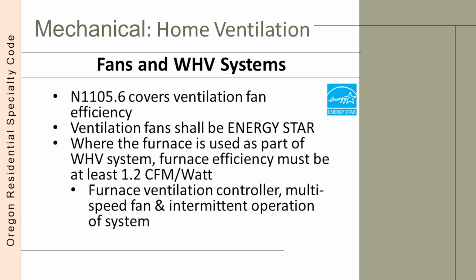Let's discuss fans and whole house ventilation systems. Section N1105.6 covers fan efficiency. All ventilation fans are required to be Energy Star fans. It's easy to verify with the Energy Star label on the fan. In addition, the 2023 ORSC has a new requirement for whole house ventilation systems that use the central furnace as the outdoor intake fan. These systems are known as central fan integrated systems. The requirement is for the furnace to deliver the ventilation air at a rate of at least 1.2 CFM per watt of fan energy. To achieve this level of efficiency, the furnace would need to be a multiple speed or variable speed fan, and there would be a necessary ventilation controller to set up intermittent operation of the furnace fan to accomplish this operation.